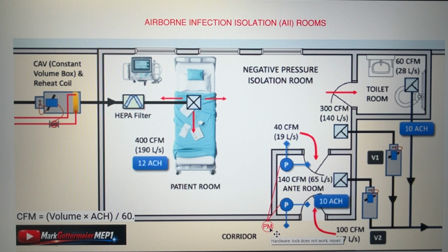If that anteroom was to be open while this bed was occupied for too long, there would be an audible alarm on that pressure monitor that would alert the staff to make sure that the doors get shut. And if it goes on for a set amount of time, the building management system, if it's in place, would also pick that up and alert facility staff that these doors were left open as well.